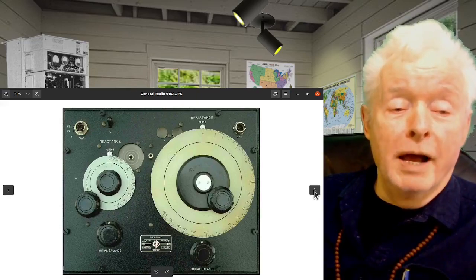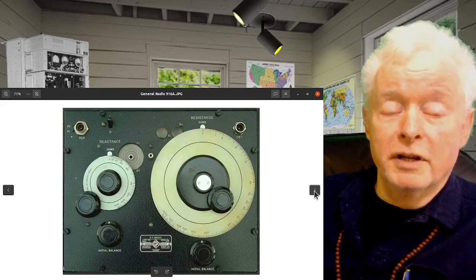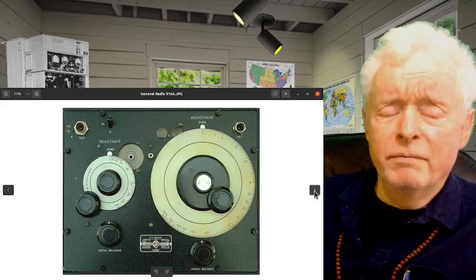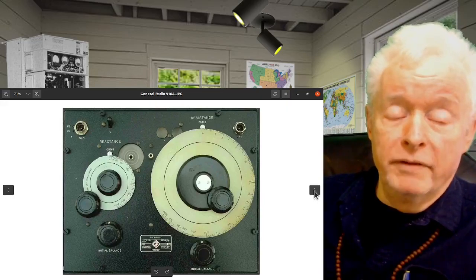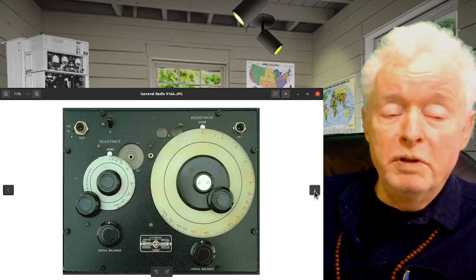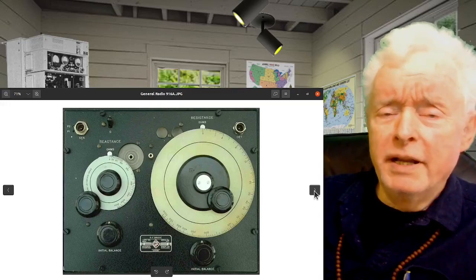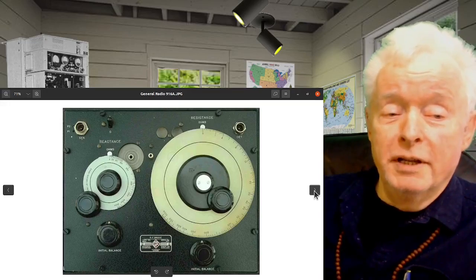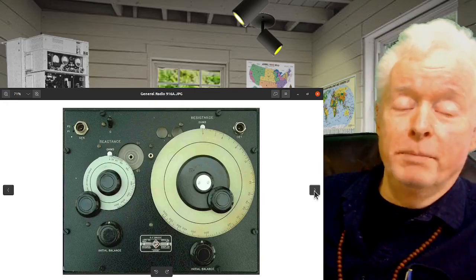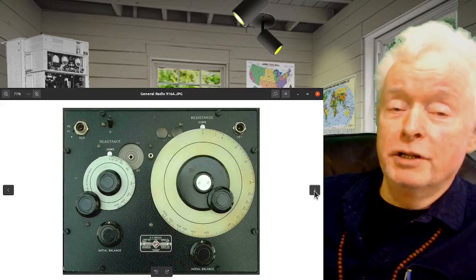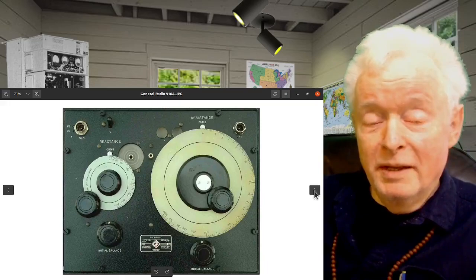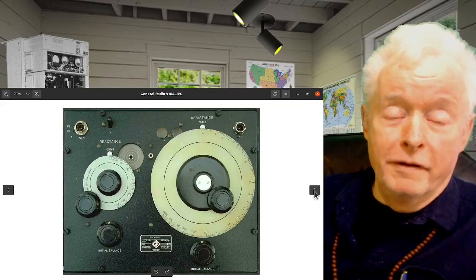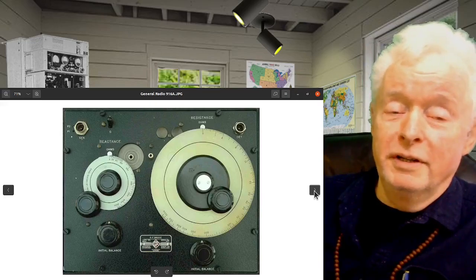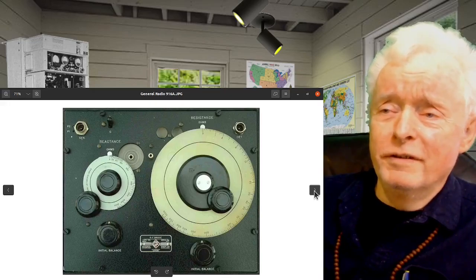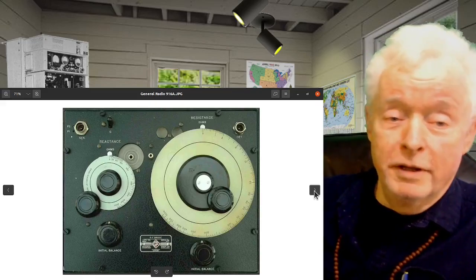If you look at the left knob here, you'll notice that it covers a circular portion of the faceplate that is kind of light gray in contrast to the dark gray of the case. And it has a silver middle. Looks like a circle, possibly a hex. It is a hex. That is a threaded input, and you connect what you're measuring to that point. It measures the impedance of that point in relation to the case of this equipment. Now, that is significant at RF, where you want to reduce all the variables. And it makes this a little difficult to use if you're not used to thinking in terms of stray reactance, stray capacitance, stray inductance, and such things.